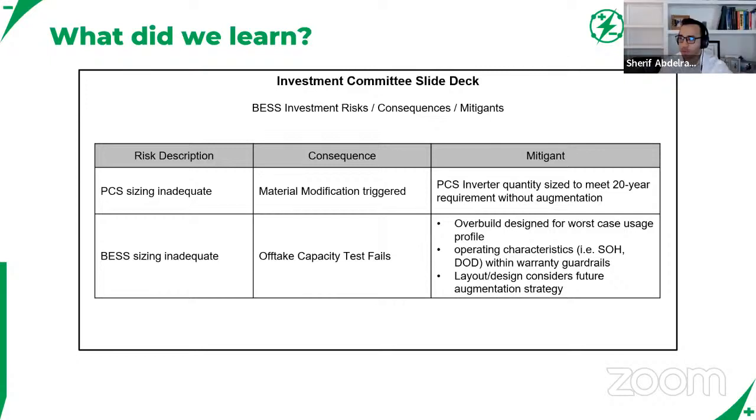I'll just add one thing on top of that. Sometimes, as you look to the risks, the mitigation is just don't, right? I've been puzzled by the number of projects I've seen assuming a very smooth DC augmentation throughout. I've seen some strategies assuming we're going to be adding new battery racks every year. This is DC augmentation. We're just adding battery racks year over year over year.